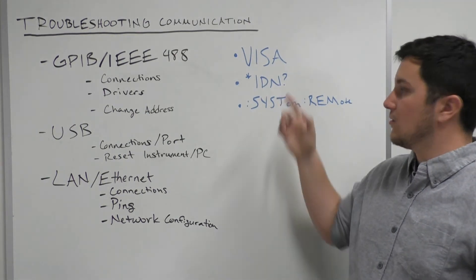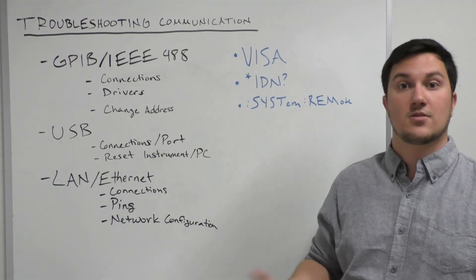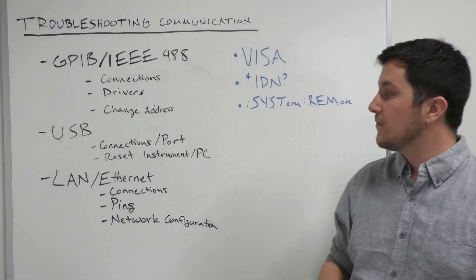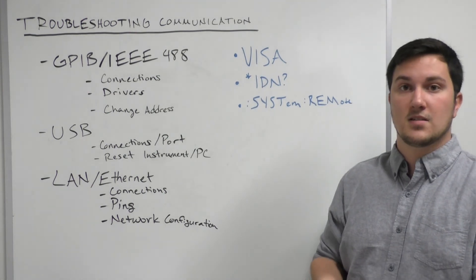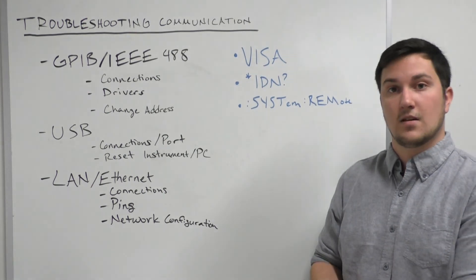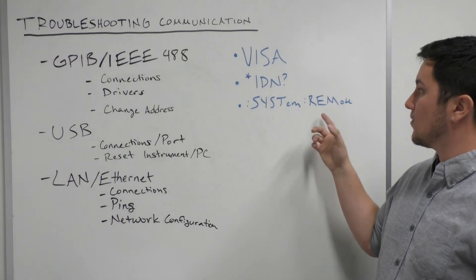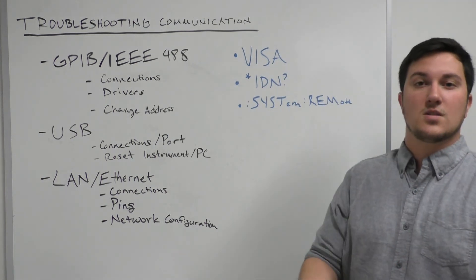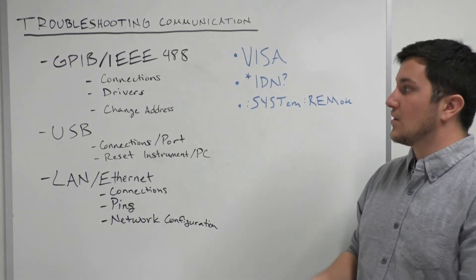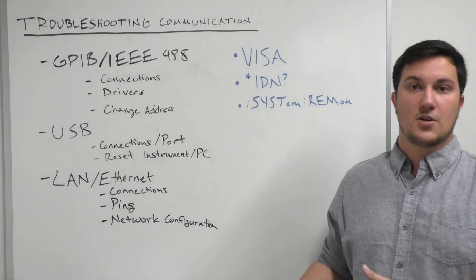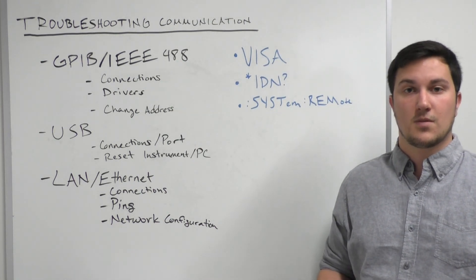This will tell you if you're getting an identification string from the instrument and if your PC and instrument are actually communicating. If you're still finding that your instrument is in local mode and not in the remote command set, you can send a system remote command and that will force the instrument into remote mode. If you continue to have any further issues with communication, you can contact us at Tektronix Technical Support — we'd be happy to help.